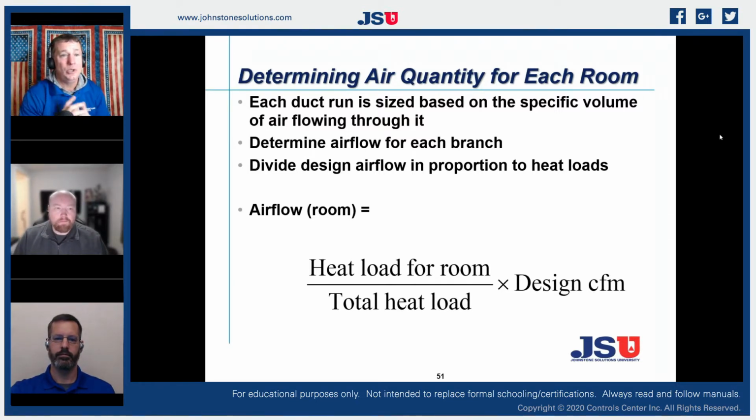So we talked a little bit about using duct calculators to design HVAC systems and to calculate airflow capacities through our ductwork. So now I want to start jumping in for a couple weeks and talking about laying out ductwork and doing duct design with our calculator. This week we're going to focus on standard calculations, and then next week we're going to focus on using an adjusted calculation based on your total effective length of your ductwork, so that we can calculate exactly the static pressure that we need to keep within our parameters, because our goal is to stay around 0.5 inches of static on our blower.